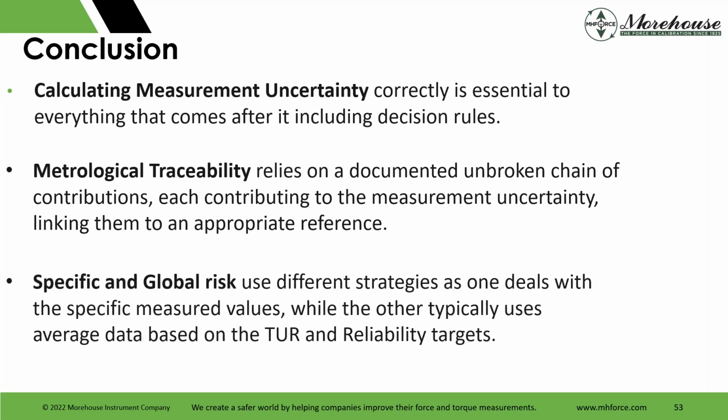And specific and global risk use different strategies, as one deals with a specific measured value, while the other typically uses average data and TUR reliability targets.